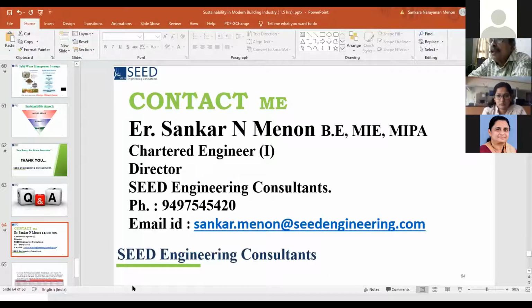Of course, then there is a question of fresh air. For fresh air, you will have a rooftop fresh air unit, and that has to be transmitted into each location through the ducts. But when you compare the amount of air which is used for fresh air requirement, for upgrading the indoor air quality, the volume being small, your ductwork will be smaller. But if the entire air is to be recirculated, including the recirculated air, your volume will be high. So for a very large building, you should go for a chiller system.